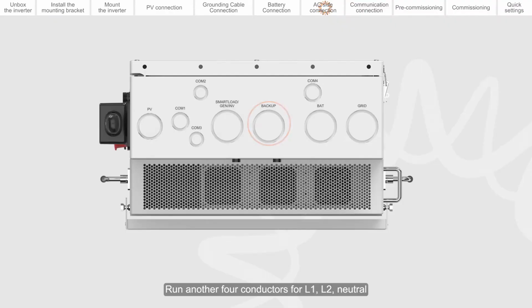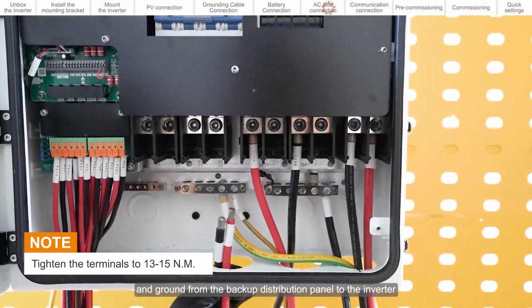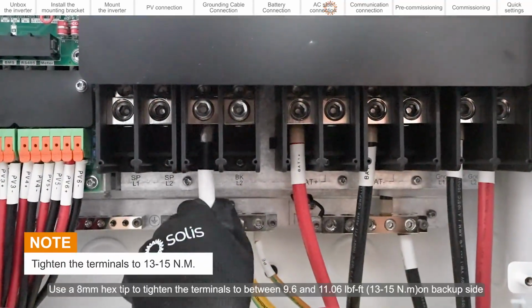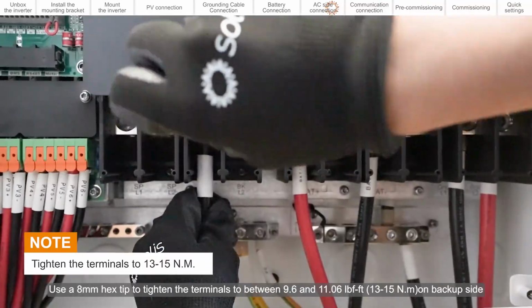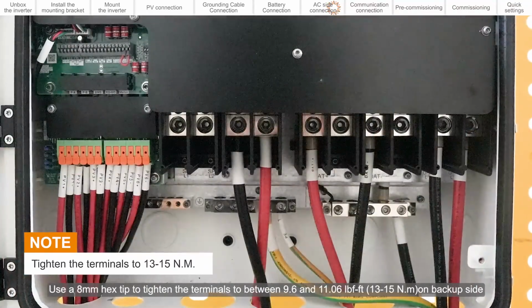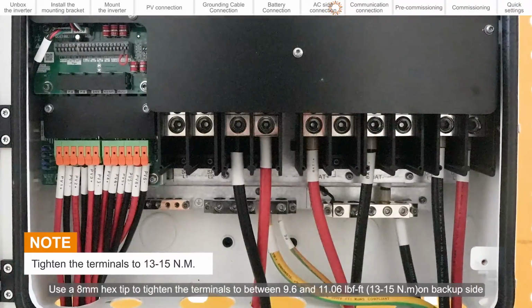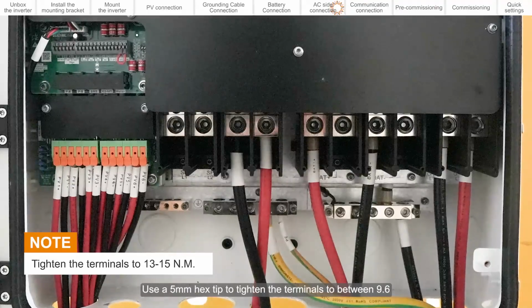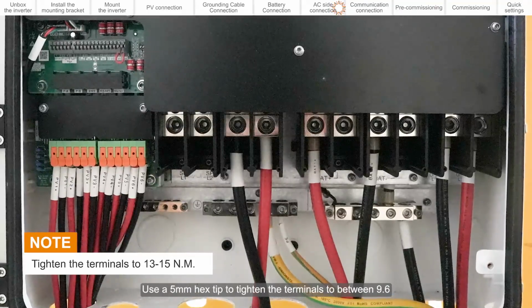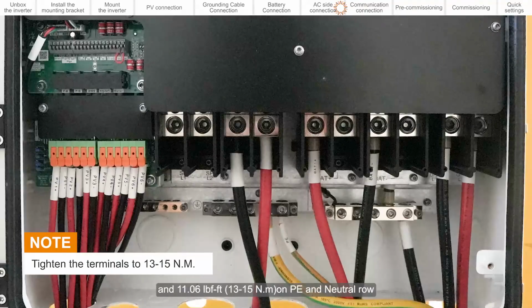Run another 4 conductors for L1, L2, neutral, and ground from the backup distribution panel to the inverter. Use an 8mm hex tip to tighten the terminals to between 9.6 and 11.06 lb-ft on the backup side. Use a 5mm hex tip to tighten the terminals to between 9.6 and 11.06 lb-ft on the PE and neutral route.